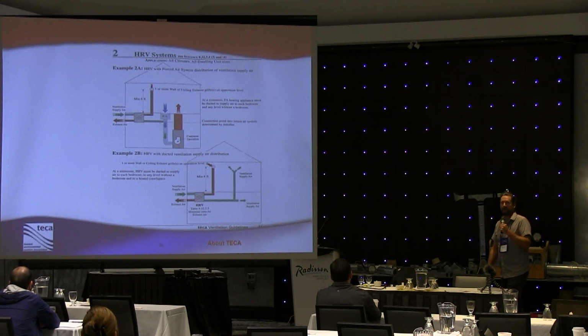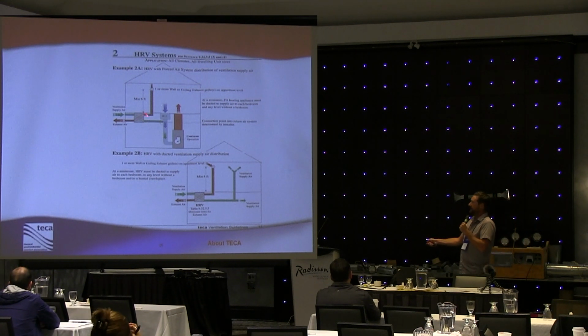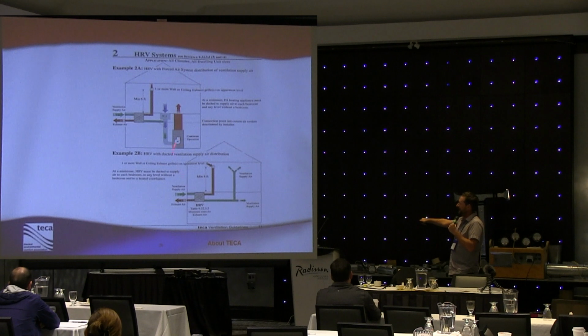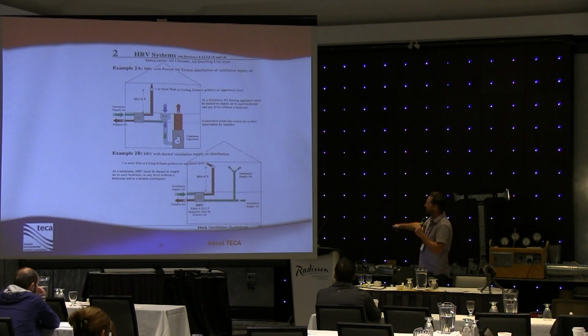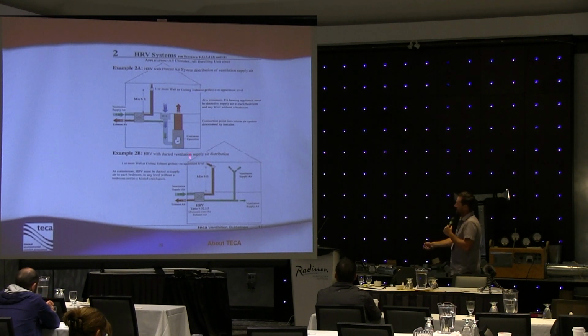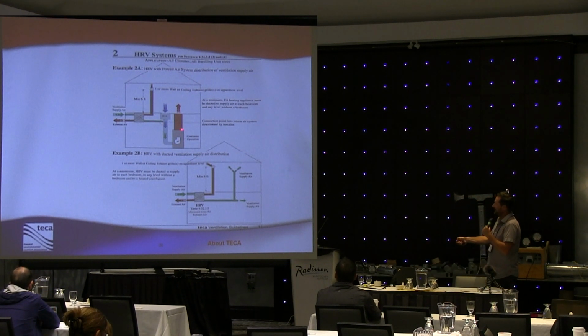However, we are running another fan. Typically HRVs have two fans in them, so there is another electrical impact with that. We've got the electrical impact of the furnace motor, but we don't have a principal exhaust fan anymore. Our principal exhaust fan becomes that HRV. That's a system paired off with a forced air heating system.